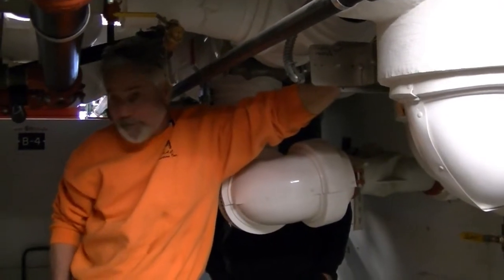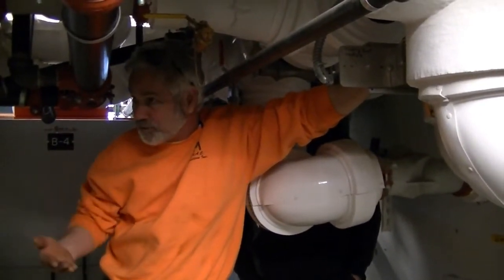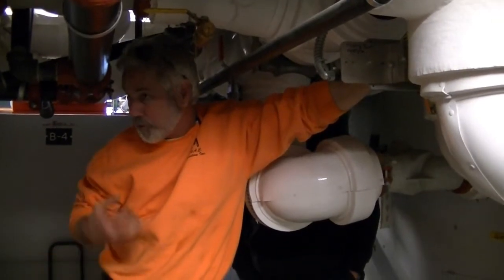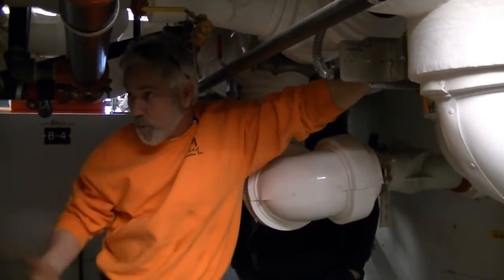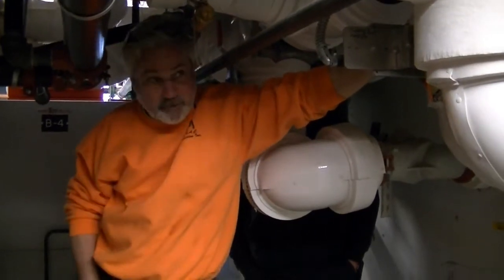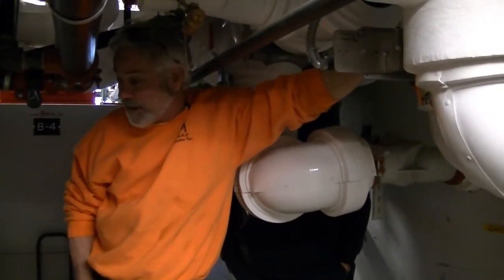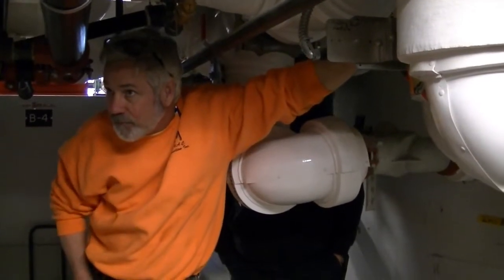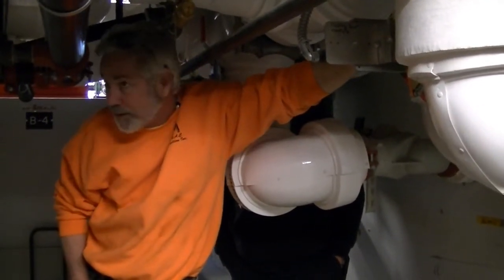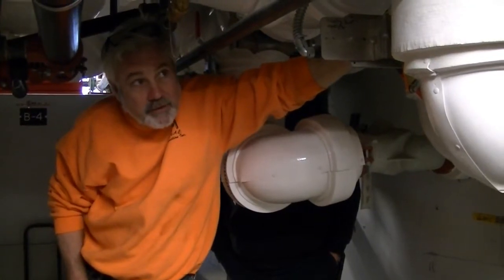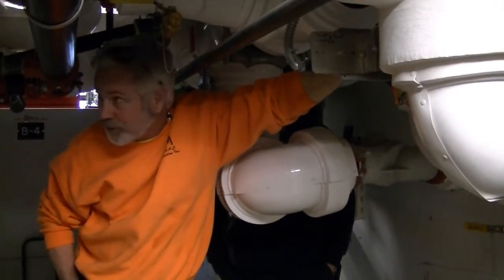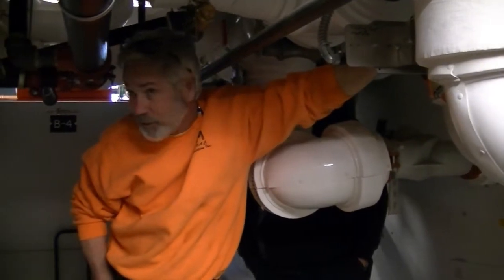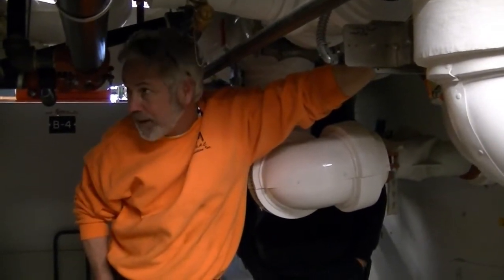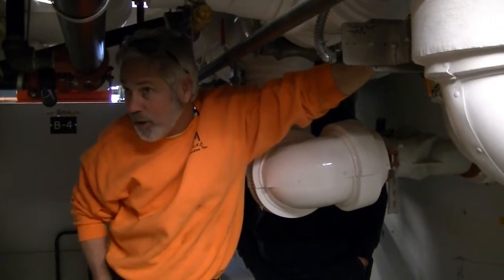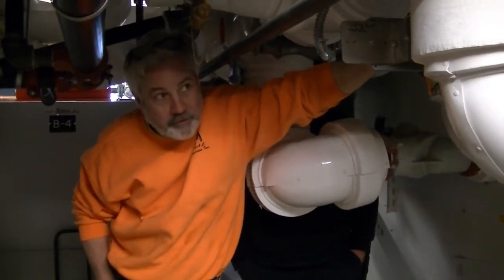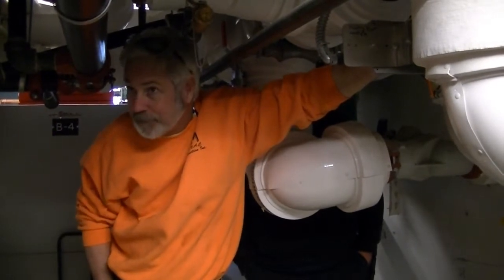Okay? What happens is when you start burning chemicals, you can create resins, you can create acids, you can eat away at heat exchangers by doing that. I mean, it's not uncommon for it to happen. I've had customers with furnaces not even a year old, and it just crumbles in front of you because somebody spilled a bucket of bleach on the floor and didn't clean it up. And those fumes went through the flame, and when it went through the flame, it turned into acid, hydrochloric acid, and it ate right through the heat exchanger. So yeah, stuff like that can happen.